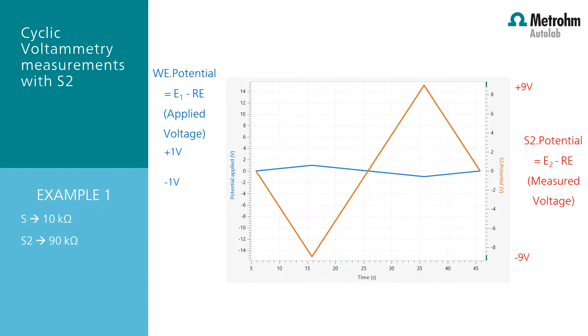This plot shows the working electrode potential, the blue line, which is set in the main parameters in the Nova software — from 0 volt to plus 1 volt, vertex to minus 1 volt, and back to 0 volt again. This is the potential applied between the sense and the reference electrode. The red line shows the measured voltage between the second sense and the reference electrode, which is the measured S2 potential. As you can see, when the working electrode potential is positive, the second sense potential will be negative. This is due to the definition of the sense and the second sense versus the reference electrode, respectively. You will find more information about this topic in the Nova user manual.